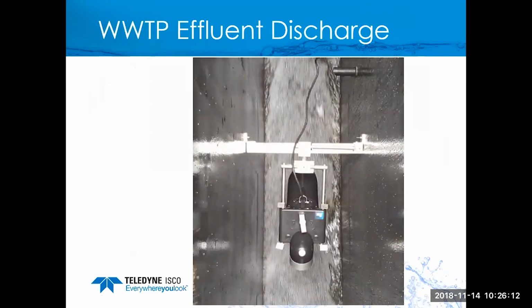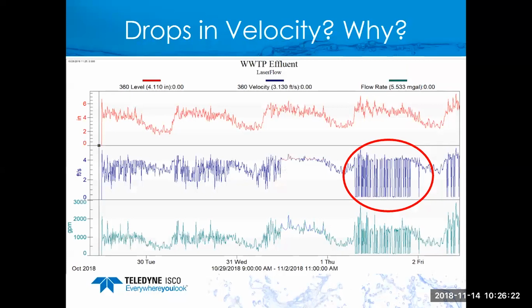But this is how they installed the lasers. They went in, they put a homemade bracket across there, lasers mounted over that channel. So initially we put that in, and the customer asked, is it going to work? We honestly didn't know how well due to the amount of turbulence and foam, but it was like, let's go ahead and put one in and see. Initially, what we found is data that looked like this. We had drops in the velocity, and they weren't dropping to zero, but they were dropping down to a very low velocity. So trying to figure out, why is this happening? Is there anything we can do to make it work? Otherwise, you were going to have to go through some pretty extensive reconstruction, put in some flow straighteners and baffles and all kinds of stuff.